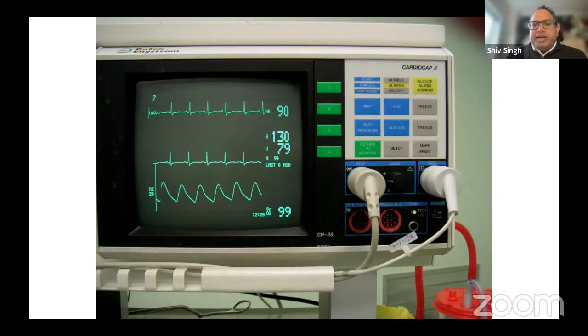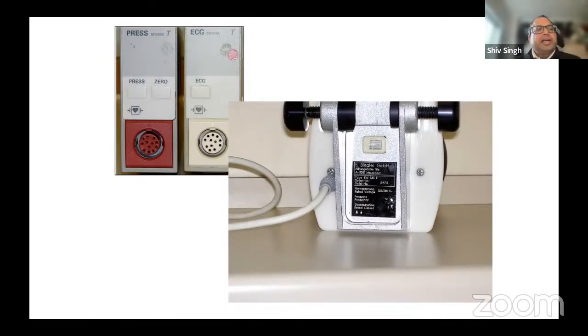So every equipment that is connected to the patient has a symbol associated with it. Okay, I don't know whether you're able to see this clearly or not. So you have the ECG, which has got a heart inside a box. You have the pressure transducer area, which is again a heart in a box. ECG or SpO2 has got a man inside a box. Okay. I'll show you some more of them much more clearly. This is the pressure transducer cable. You can see a heart inside a box with cables.